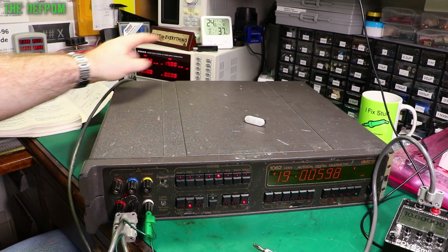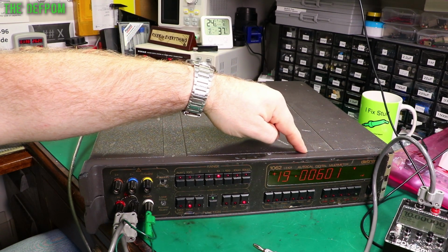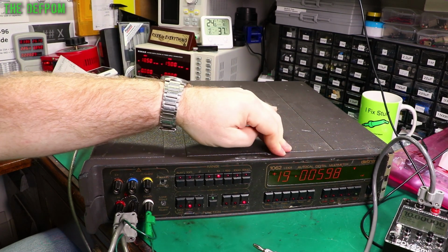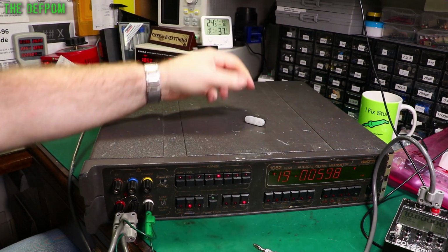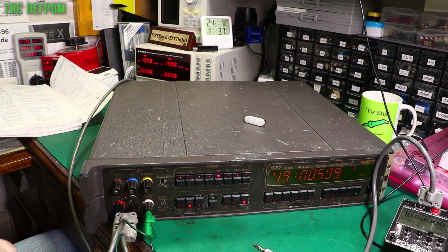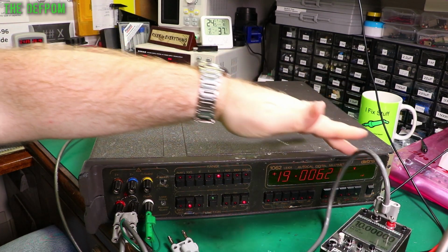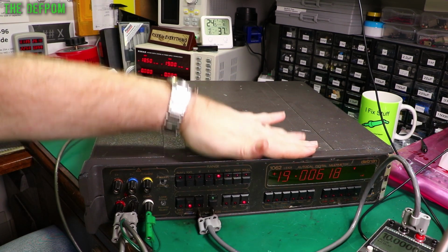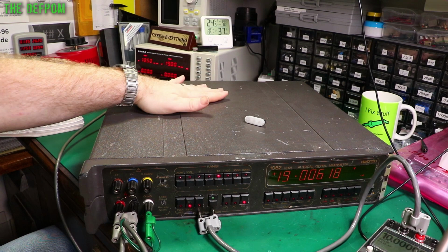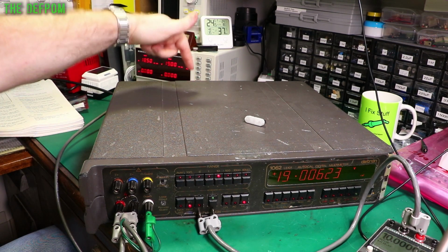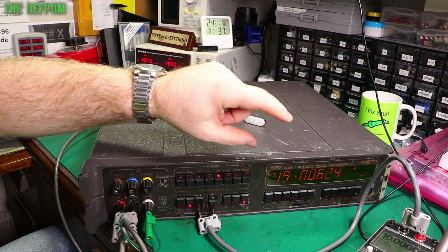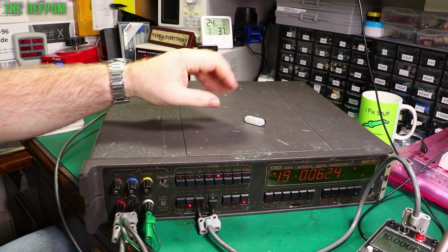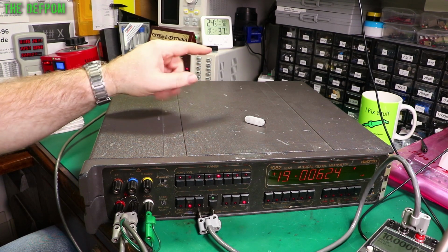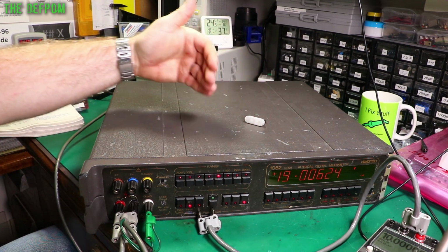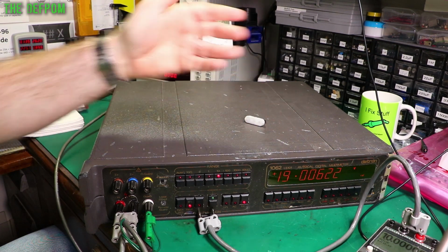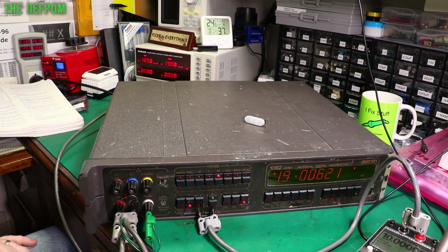Okay, so that says 19.006. My Siglent says 19.006. That's linear, or at least pretty damn close to it. So I'm happy with that adjustment there. That's good. That linearity looks absolutely fine, well within what I expect it to be. So I don't actually have to do adjustment. That's R23 just over here, which is for doing that linearity adjustment. You make sure there's an offset difference between the scaling, and you do a calculation on that, and you work out what you should set it to. So that way it's linear across the range, and obviously I don't think it needs to tune because it's close enough. I think it's basically right. I'm just going to leave that alone.